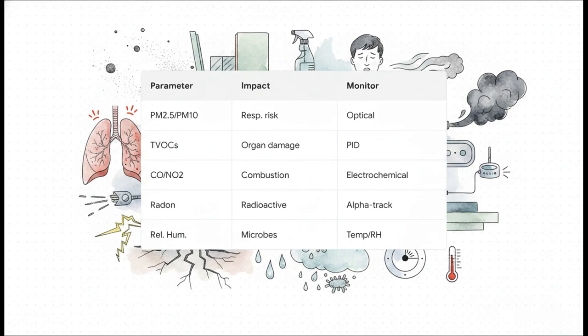Then we have TVOCs, total volatile organic compounds. These off-gas from building materials and cleaning supplies, causing everything from mild fatigue to actual organ damage. We monitor those using photoionization detectors. We also have to track dangerous combustion byproducts like carbon monoxide and nitrogen dioxide using electrochemical sensors. Plus, we absolutely must account for radon, a radioactive soil gas tested through alpha-track passive sampling. And finally, relative humidity. We track it because it directly drives microbial growth and completely dictates thermal comfort. Mastering these parameters, that's the floor, not the ceiling, of elite building performance.